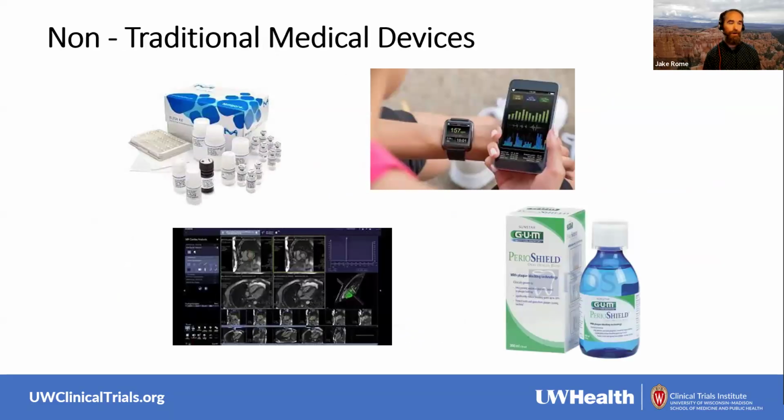But then we also have this category of what I'll call non-traditional medical devices. These are things that are becoming more popular in certain instances, but it's things like in vitro diagnostic products. So tests, assays that we're doing, the drug tests that you're picking up at Walgreens, or COVID tests that we're all very familiar with. Software, wellness software, heart rate monitors, those can be medical devices as well, as can diagnostic imaging machine software, and even sort of interesting things like mouthwashes.